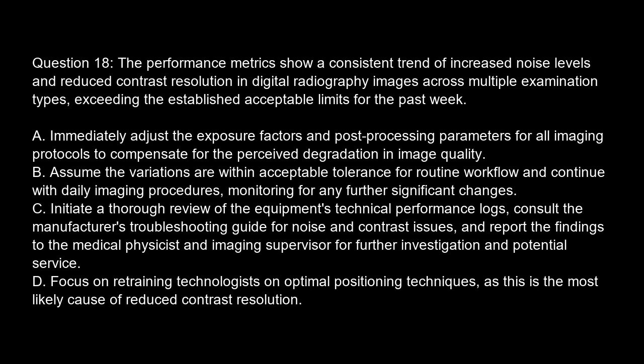Option B. Assume the variations are within acceptable tolerance for routine workflow and continue with daily imaging procedures, monitoring for any further significant changes. Option C. Initiate a thorough review of the equipment's technical performance logs, consult the manufacturer's troubleshooting guide for noise and contrast issues, and report the findings to the medical physicist and imaging supervisor for further investigation and potential service. Option D. Focus on retraining technologists on optimal positioning techniques, as this is the most likely cause of reduced contrast resolution.